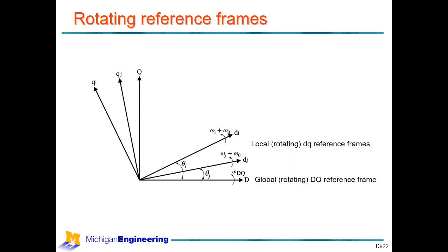It gets a little complicated here. One important thing: across an entire grid, there's a global rotating reference frame, using capitals DQ, standing for direct-quadrature. Each device, like an inverter or synchronous machine, has its own local rotating reference frame as well. The upcoming slide looks at how to rationalize the connection between the two. The key point is that this rotating reference frame turns AC signals effectively into constants that can then be manipulated in the control strategy.